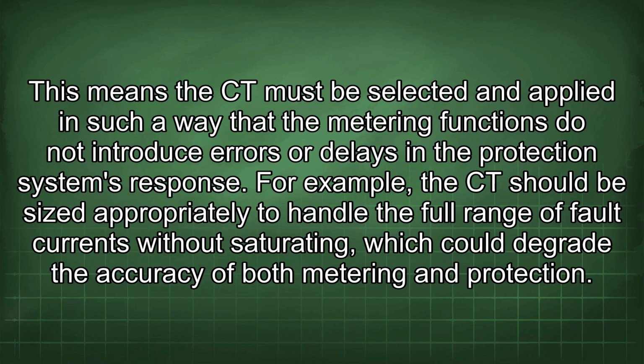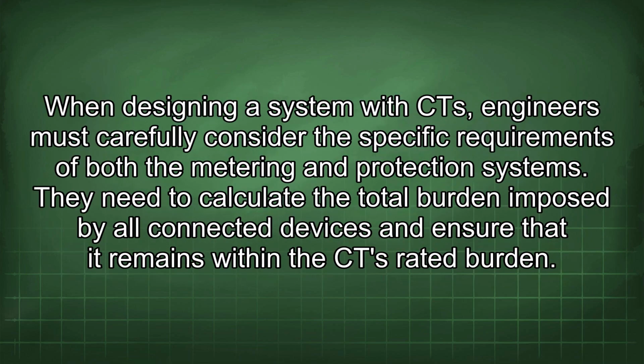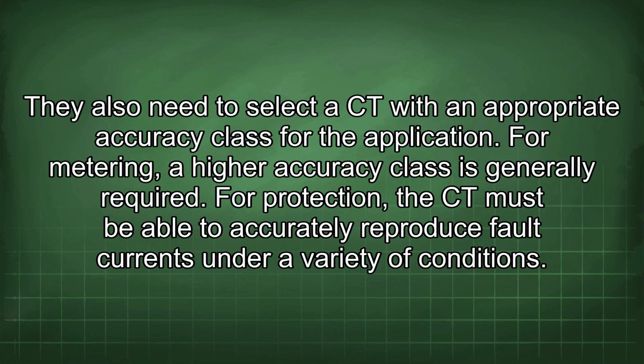For example, the CT should be sized appropriately to handle the full range of fault currents without saturating, which could degrade the accuracy of both metering and protection. When designing a system with CT, engineers must carefully consider the specific requirements of both the metering and protection systems. They need to calculate the total burden imposed by all connected devices and ensure that it remains within the CT rated burden. They also need to select a CT with an appropriate accuracy class for the application. For metering, a higher accuracy class is generally required. For protection, the CT must be able to accurately reproduce fault currents under a variety of conditions.